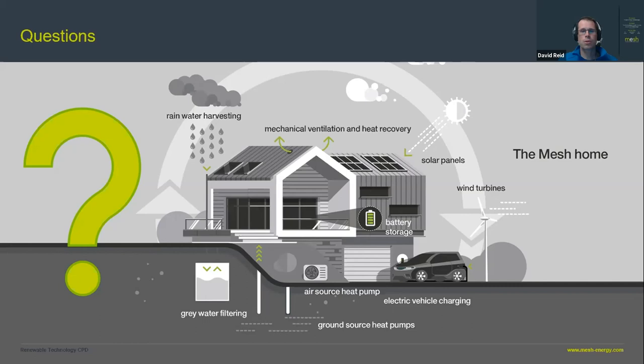The reason the front lawn was becoming uneven was because they were freezing the ground, and then over the summer it was defrosting, and you get ground heave from the ground freezing and unfreezing. Unfortunately, the only way of curing that is to extend the existing collector system. But of course, you then have to effectively oversize the system to allow the bit you've already damaged to recover. So you end up in a worse point than you would have been if you'd done it right first time.